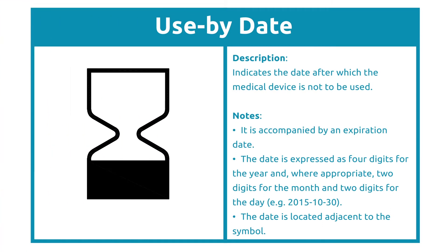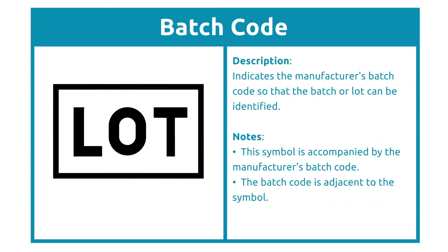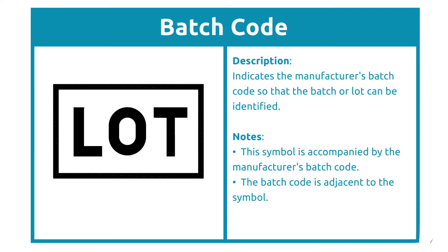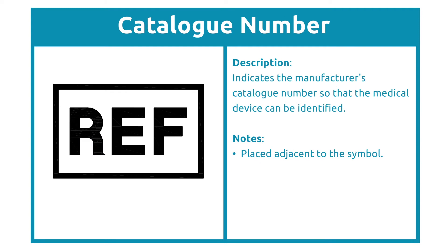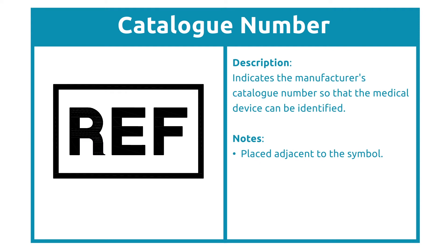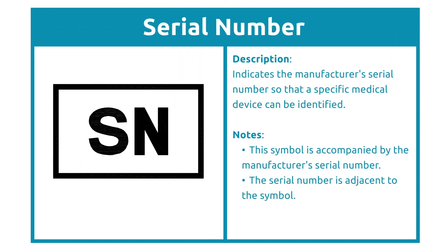The Use By Date symbol shows the product has a shelf life. This symbol must have the 4-2-2 format date as well, and indicates the date by which the product must be used. The Batch Code symbol is an identification marker for the product — the manufacturer's batch code is placed next to this symbol. Another identifying marker is the catalog number, where the manufacturer's catalog number is placed next to the symbol. The third product identifying marker is the serial number.